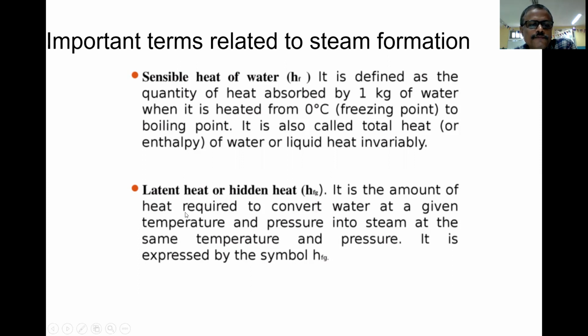It is the amount of heat required to convert water at a given temperature, which is nothing but the saturation temperature and pressure, into steam at the same temperature and pressure. It is expressed by the symbol HFG in our steam tables. So what is latent heat? It is nothing but the amount of heat required to convert water into steam at saturation temperature.